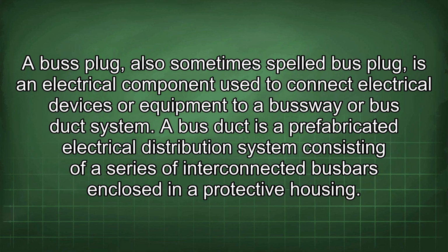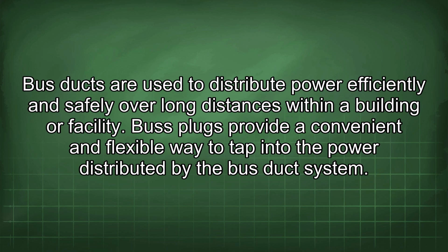A bus plug, also sometimes spelled busplug, is an electrical component used to connect electrical devices or equipment to a busway or bus duct system. A bus duct is a prefabricated electrical distribution system consisting of a series of interconnected bus bars enclosed in a protective housing. Bus ducts are used to distribute power efficiently and safely over long distances within a building or facility. Bus plugs provide a convenient and flexible way to tap into the power distributed by the bus duct system.